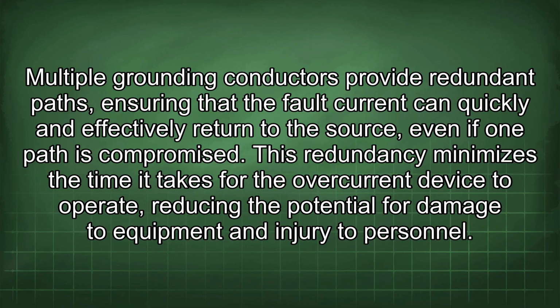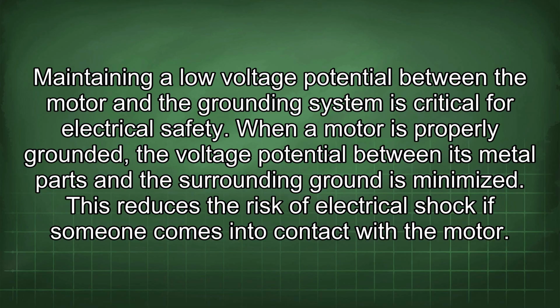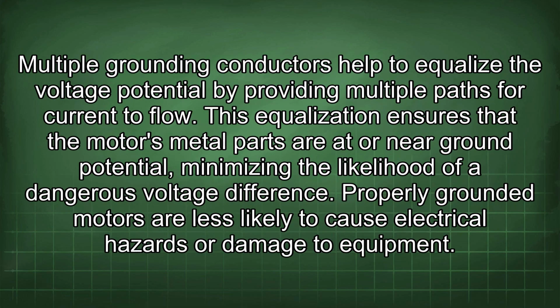Maintaining a low voltage potential between the motor and the grounding system is critical for electrical safety. When a motor is properly grounded, the voltage potential between its metal parts and the surrounding ground is minimized. This reduces the risk of electrical shock if someone comes into contact with the motor. Multiple grounding conductors help to equalize the voltage potential by providing multiple paths for current flow. This equalization ensures that the motor's metal parts are at or near ground potential, minimizing the likelihood of a dangerous voltage difference.